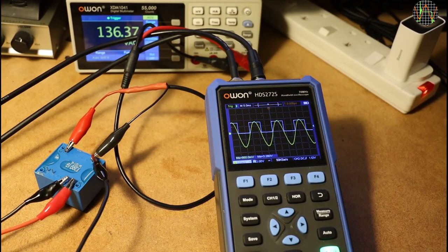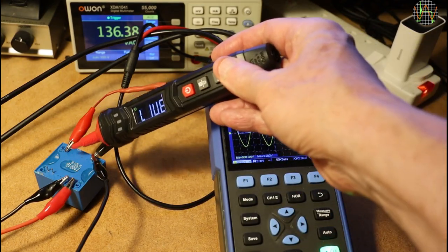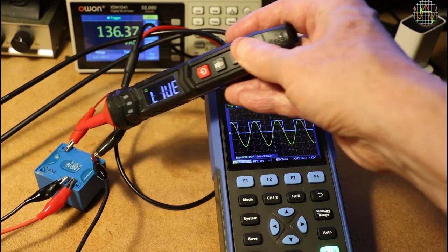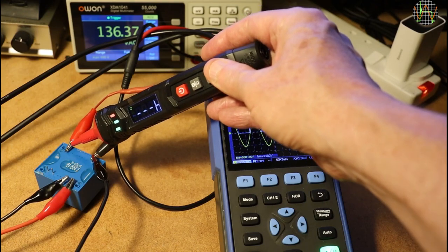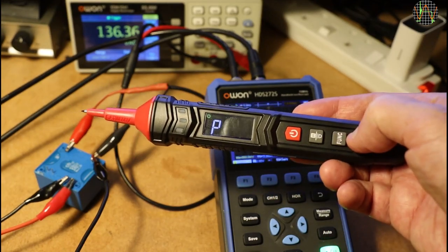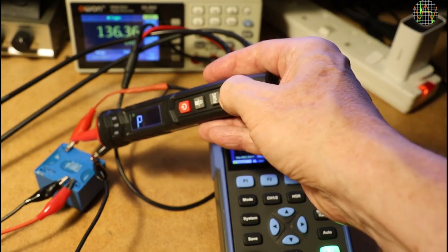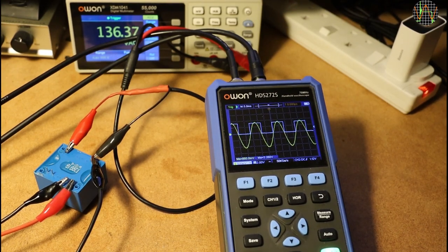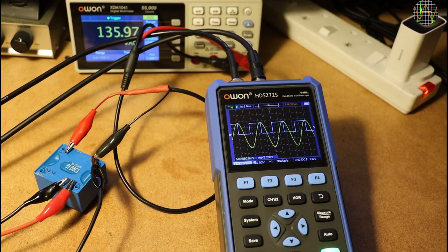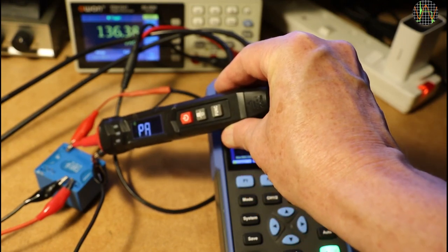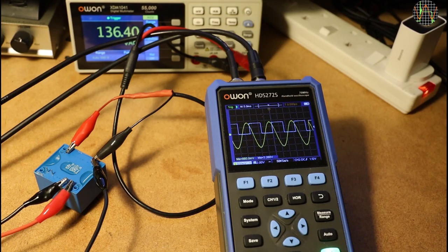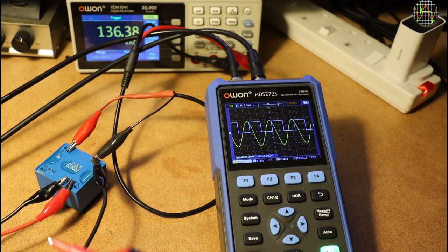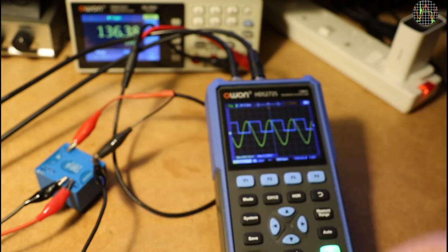For a more realistic test, I boosted that sine wave to 136V AC using the blue transformer and connected one end to the neutral or earth. Using live test, the ST120 is happy in identifying this. The phase is currently set to 0, so on with phase sequence test. The ST120 shows PA with a blinking A indicating it expects the first phase and now I have one minute to complete the whole sequence. With the first phase done, the A becomes steady and a blinking B appears. I now need to shift the phase by 120 degrees, but the ST120 does not recognize that. Shifting the phase a further 120 degrees and it still does not recognize the new phase. After one minute the display changes to PABC with P blinking to show that the test failed.